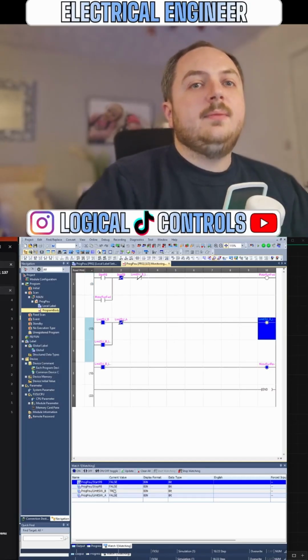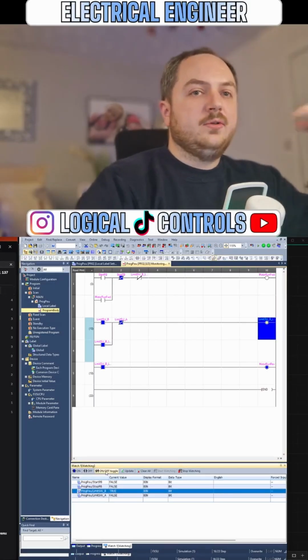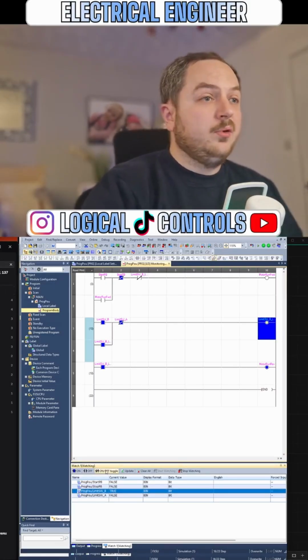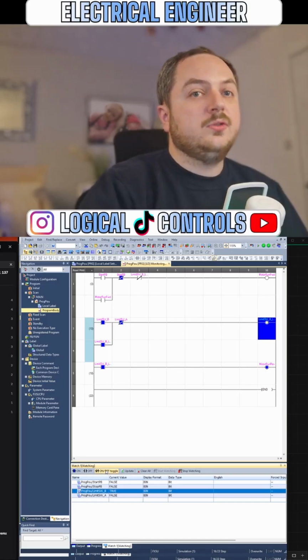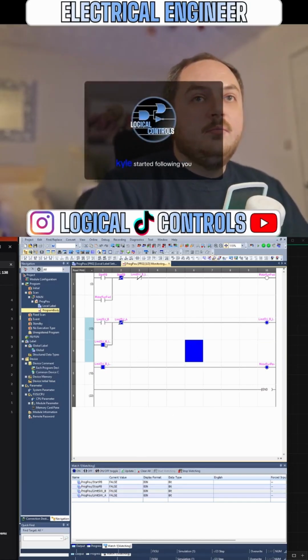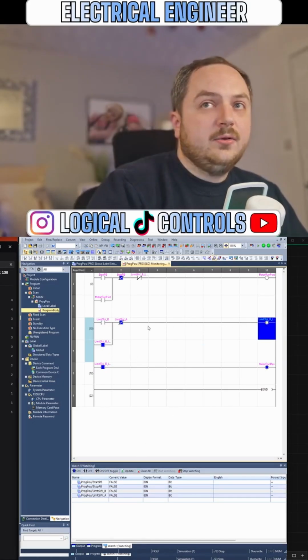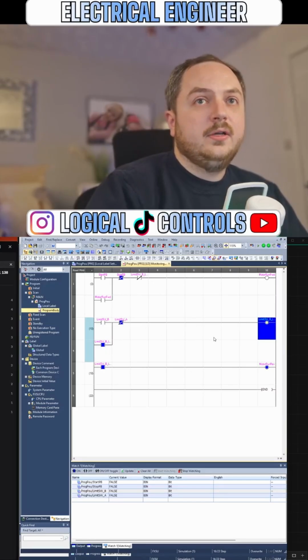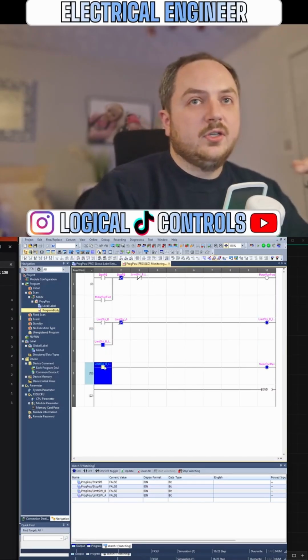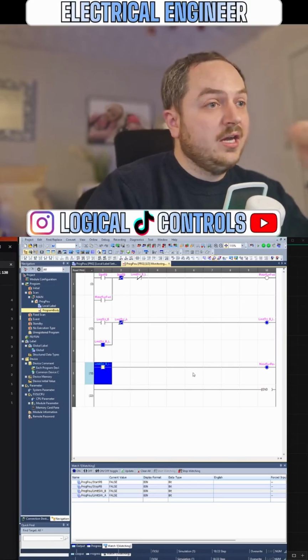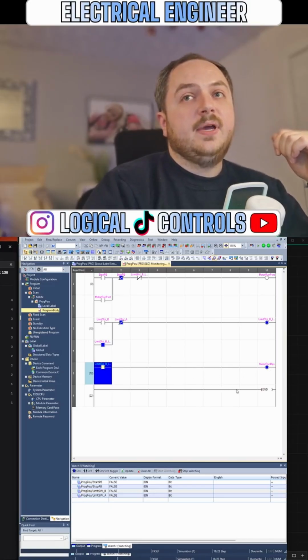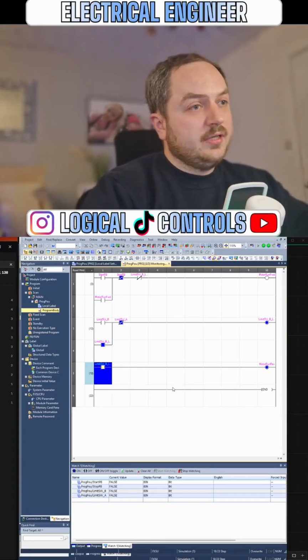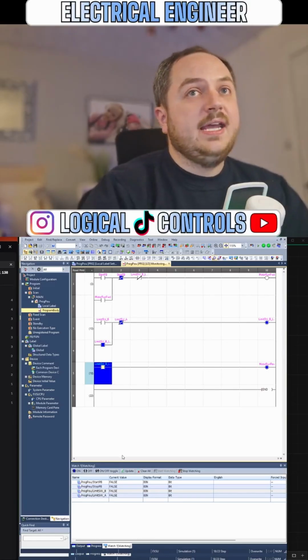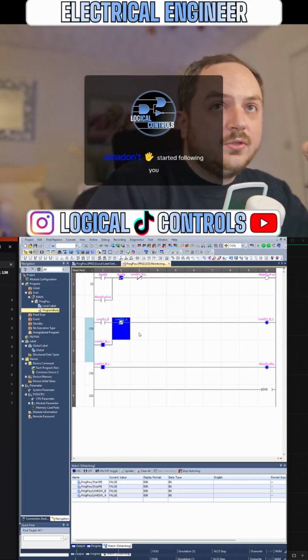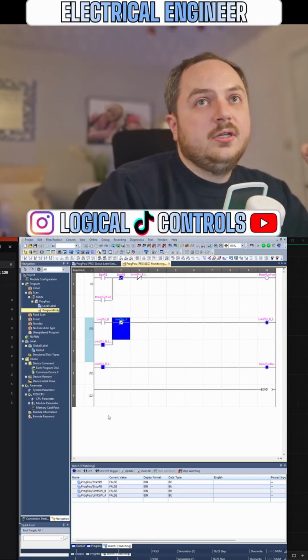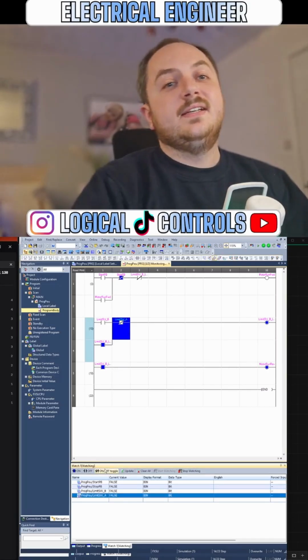Right, so we hit limit switch B and we've started going backwards now. The minute you start going backwards, at some point you're not touching limit switch B anymore, so that goes off. But because we latched it up, it's still held in - that's what this latch was all about. We're still going in reverse because limit switch B latch is what's doing our reversing. Eventually we're going to keep going back so far that we hit limit switch A. Once we hit limit switch A, that's what's going to deactivate our B latch. I'm hoping this makes sense.